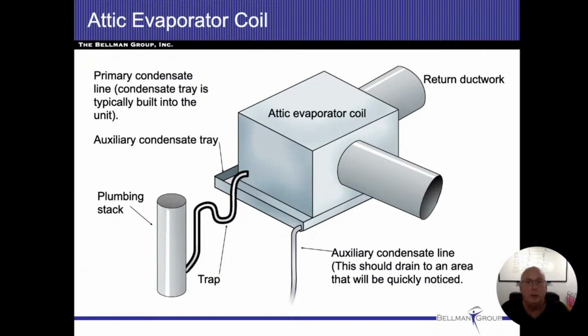All right. So here they're showing that we put a pan underneath it. We're going to have our primary drain, and this one they're taking into the plumbing stack. Because it's going into the plumbing stack, it's trapped. All right. And then the water, and that'll keep the sewer gases from coming into the house. But if that primary drain gets clogged and now water's not draining there, it's going to start leaking on the floor. That's where the secondary pan comes into play.